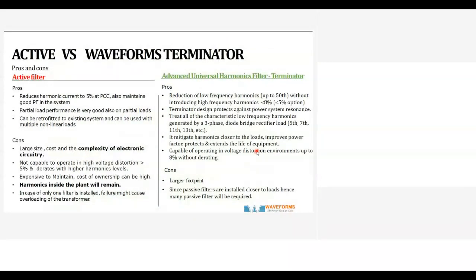So I will briefly tell you about the advantages and the disadvantages of the active filter. The active filter is a very effective filter, no doubt about it. It reduces harmonic current to 5% at PCC, also making good power factor in the system. Partial load performance is very good. It can be retrofitted to an existing system and can be used with multiple non-linear loads.